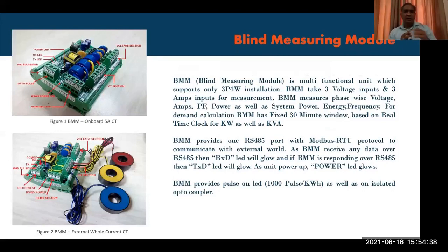So we developed a blind measuring module, a multifunction meter with everything in place, like all your powers, energies, demands, everything, but without a display. So when there's no display, how do you check readings? Through RS485, everything gets transported to the customer's screen, so the customer can use those RS485 addresses, decode them, and use that data as needed.